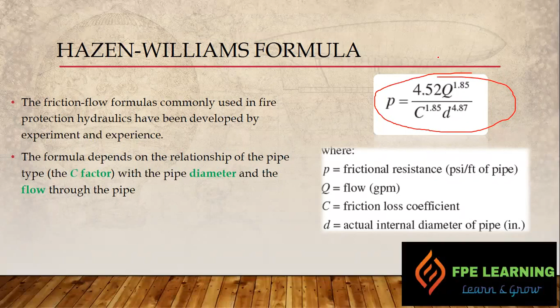Okay, so for the C value for the Hazen-Williams, I have taken two tables. The one on the left is from the fire protection handbook. The one on the right is from NFPA 13, chapter 23, tables. We can take any values, but for the moment I'm going to assume the table on the right. You can see we have different pipes: cast iron at 10 years, 15 years, 20, 30, 50, and so on. We have three different values, A, B, and C. The first one is for water which is mildly corrosive, the second is for moderately corrosive water, and the last is for water which is very severely corrosive. On the right we have the value of the C factor.